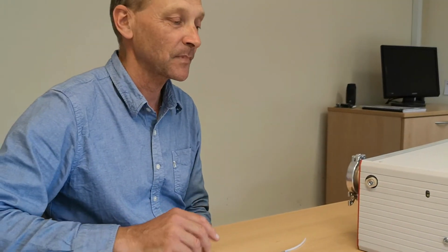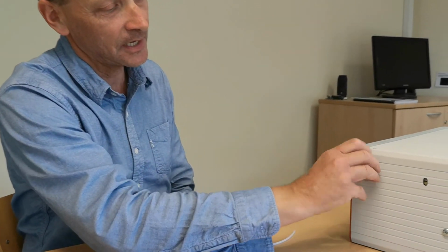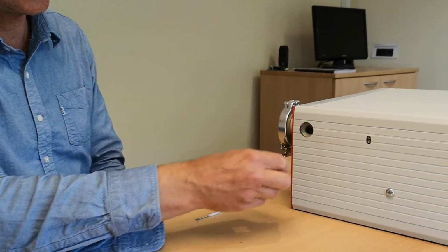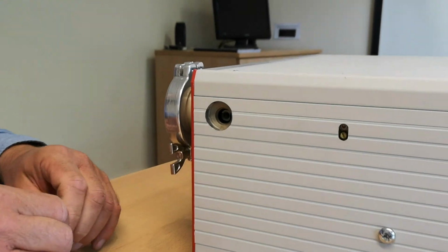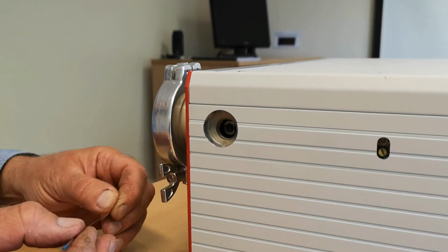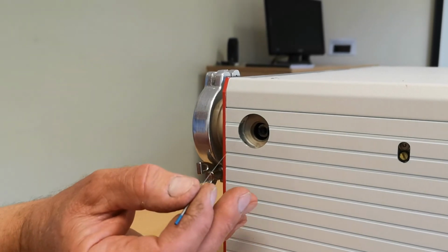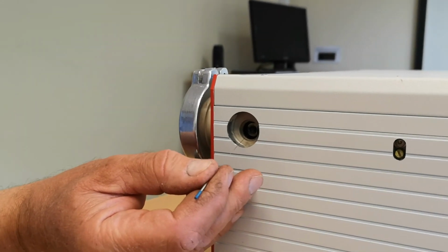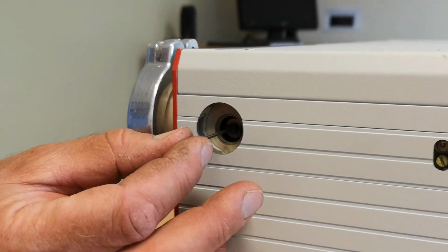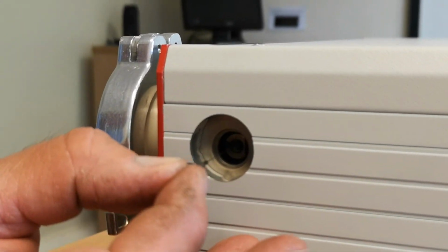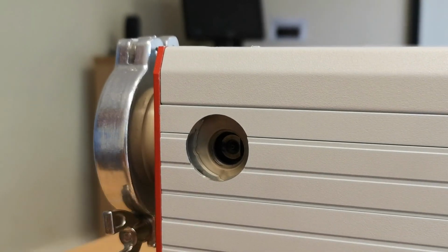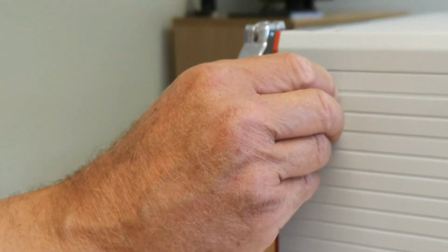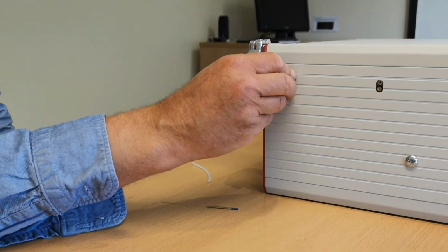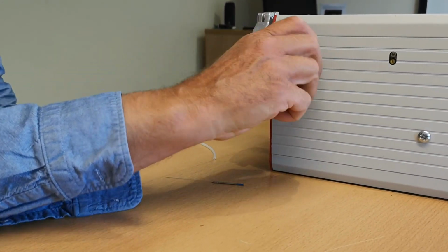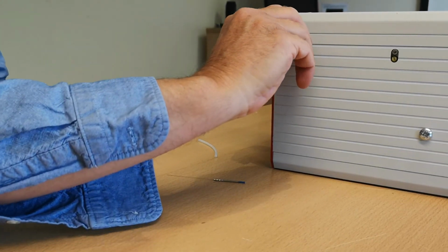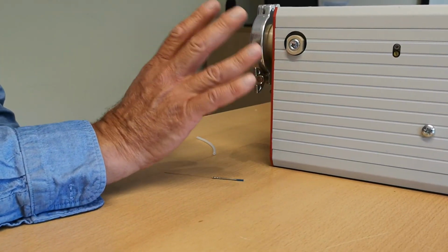Another thing to clean, especially if you're not using the sample filter, is the FID tube, which is inside the detector, which is inside the box here. So once a day, if you're not using the filter, it's important to clean out this capillary. This is a dedicated cleaning tool which is 9/1000 of an inch diameter, and this just passes through the capillary up to its shoulder, and that ensures that the capillary is perfectly clean. If you're using the instrument with the sample filter fitted at all times, then it's less important to clean this regularly, and perhaps cleaning this only once a month will be adequate.